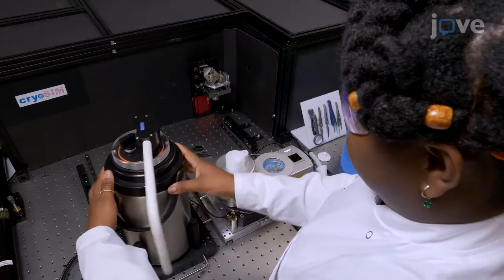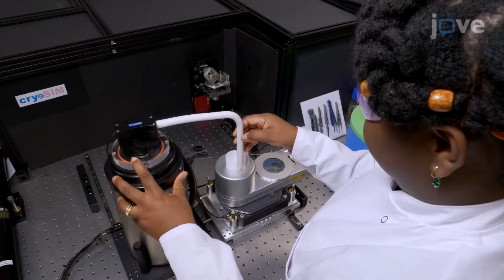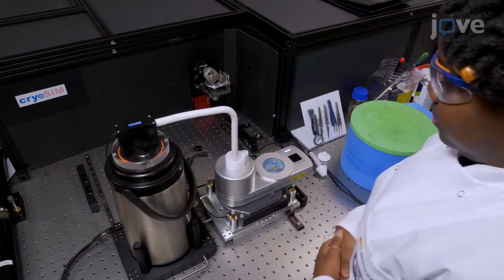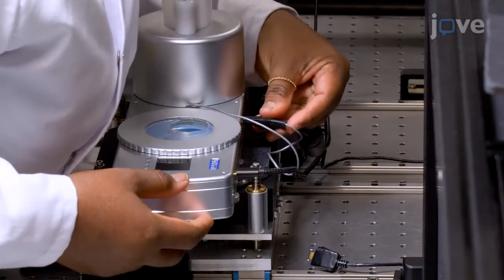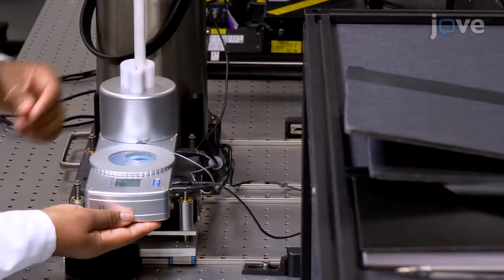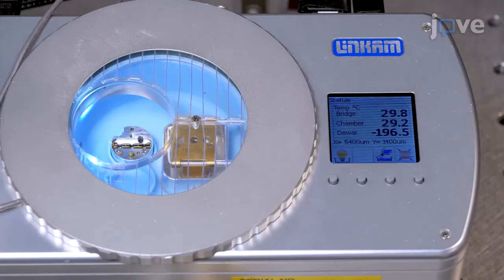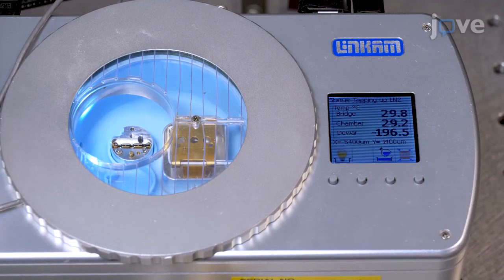Once the liquid nitrogen has stopped coming out of the outlet, place the outlet pipe over the stage dewar on the cryostage. Plug in the power source, connect the USB cable, and plug in the external dewar to the stage.